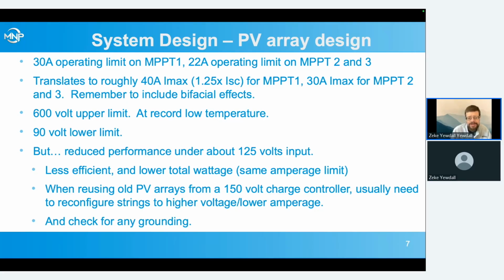This really comes into play when you're reusing old PV arrays that used to be on a 150 volt charge controller, and now you're revamping the system and putting an all-in-one in. Often we need to reconfigure the strings to be higher voltage and lower amperage.